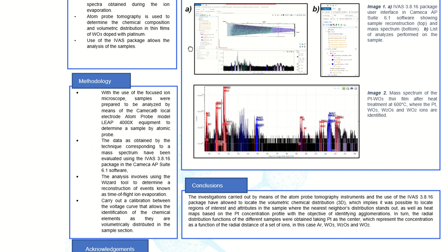The steps for doing this start with the use of the focused ion beam microscope to help us give the samples a needle shape so that they can be analyzed by means of the local electrode atom probe, model LEAP 4000X, to determine a sample by atom probe. Once this is done, the data obtained by the technique, corresponding to a mass spectrum, have been evaluated using the IVAS 3.8.16 package in the Cameca AP Suite 6.1 software.